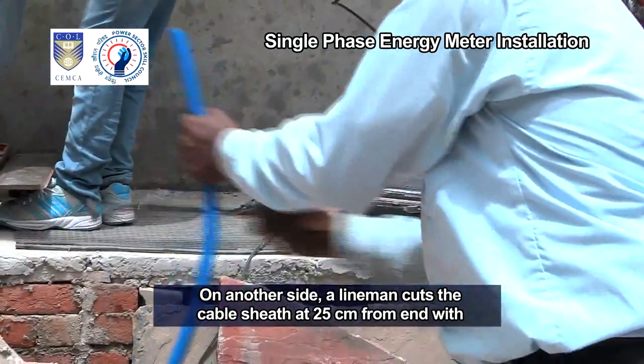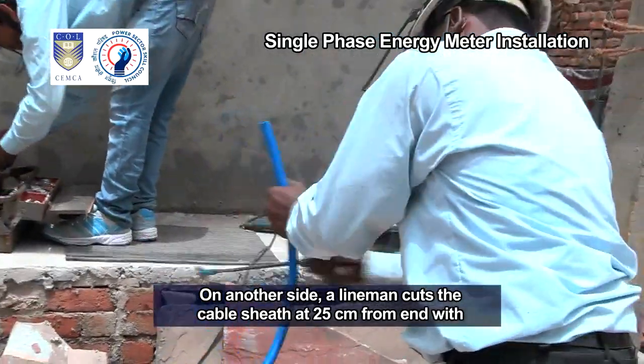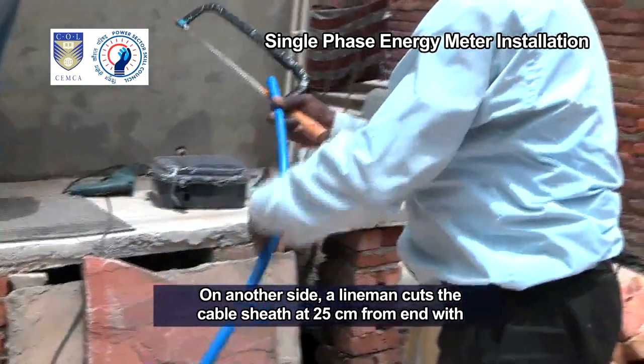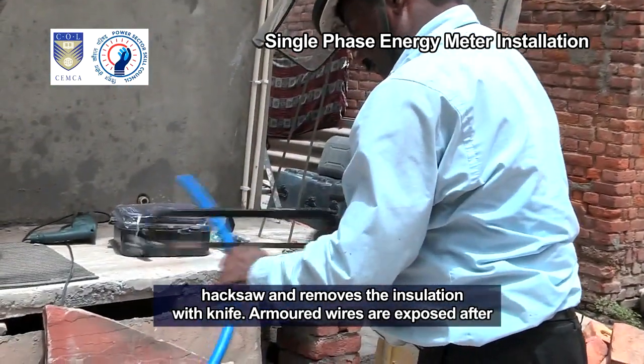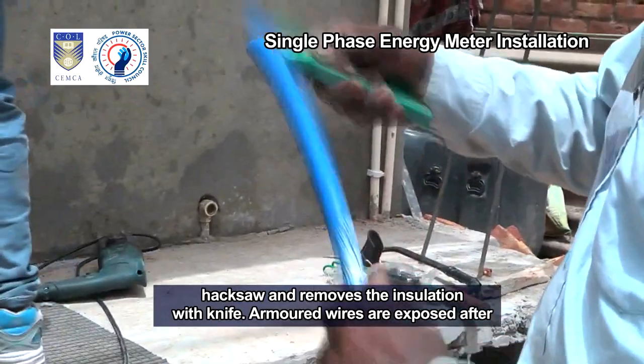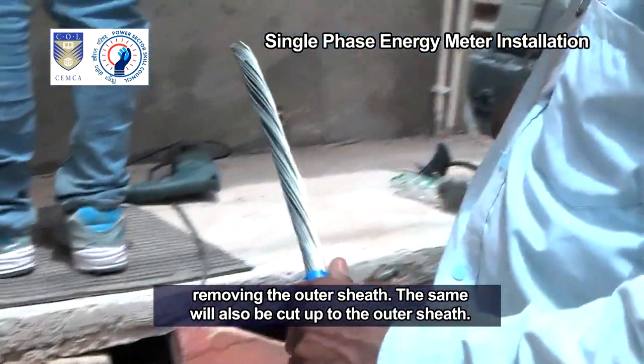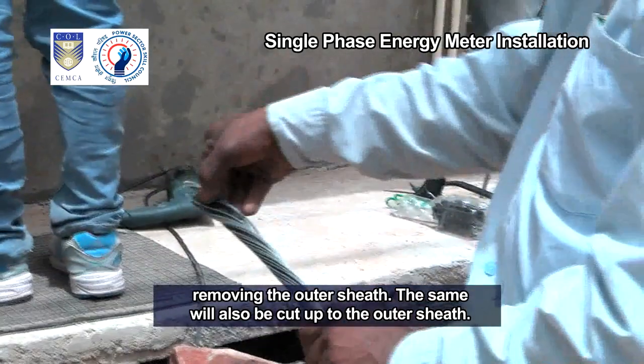screwdriver. On another side, a lineman cuts the cable sheath at 25 cm from end with hacksaw and removes the insulation with knife. Armored wires are exposed after removing the outer sheath. The same will also be cut up to the outer sheath.